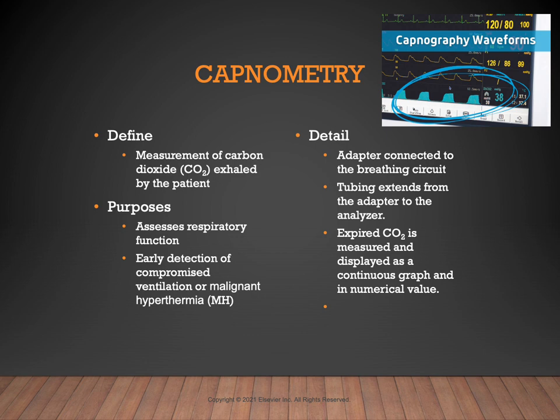Capnography, or capnometry, measures the carbon dioxide exhaled by the patient — called end-tidal CO2. This helps the surgical team assess respiratory function and can serve a critical role in the early detection of conditions such as compromised ventilation or malignant hyperthermia. Tubing extends from an adapter on the ventilator to the respiratory analyzer, and the expired CO2 is displayed in graphic and numeric forms. The machine is programmed to alarm if CO2 levels exceed preset levels.